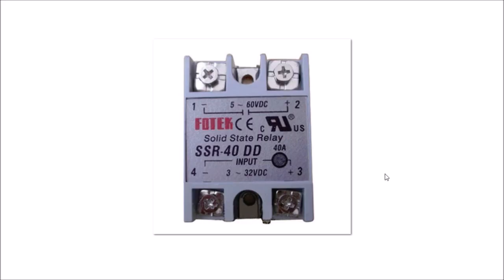Pictured here is a solid state DC relay. It has heavy duty screw terminals. The input is 3 to 32 volts DC. That's your control voltage. Apply voltage, the relay turns on. Your output is rated 5 to 60 volts DC up to 40 amps.